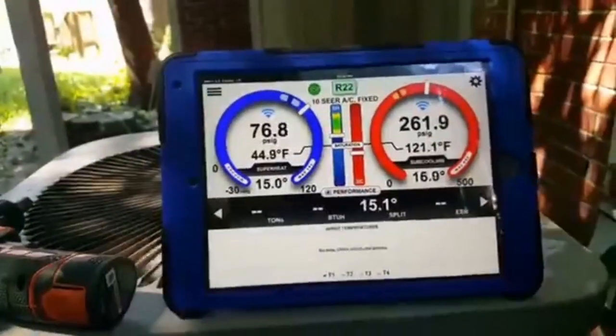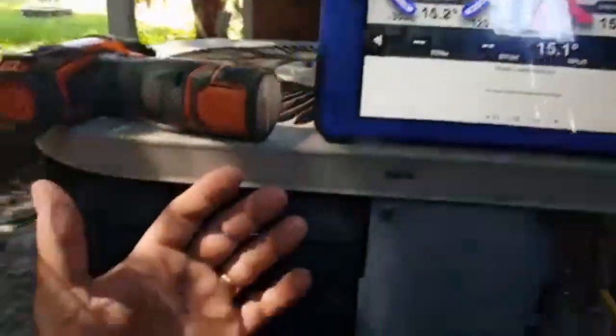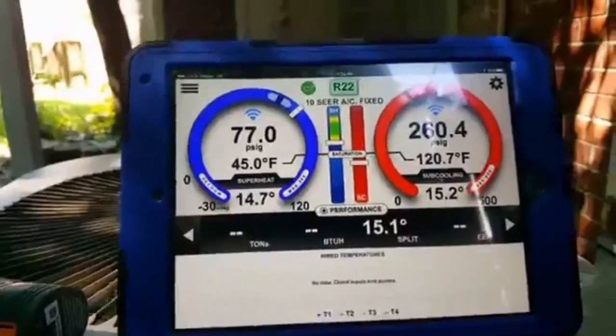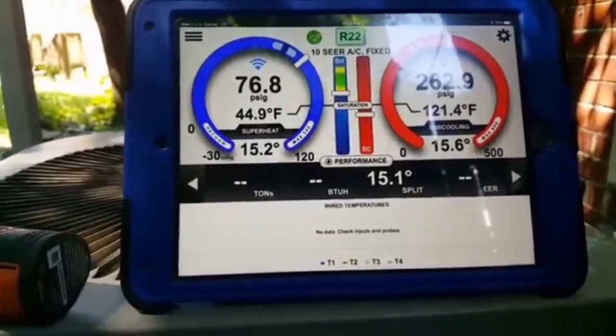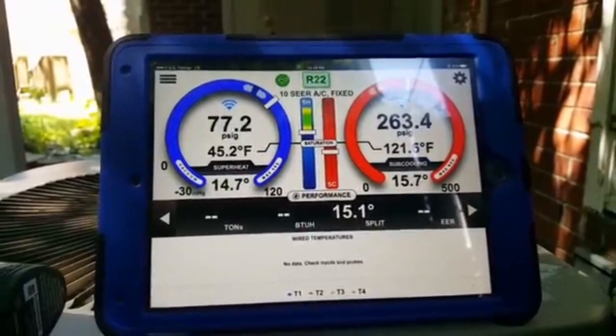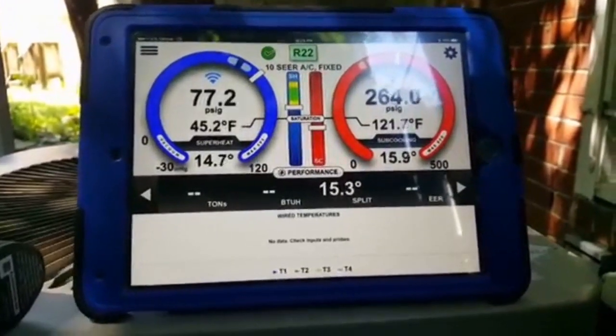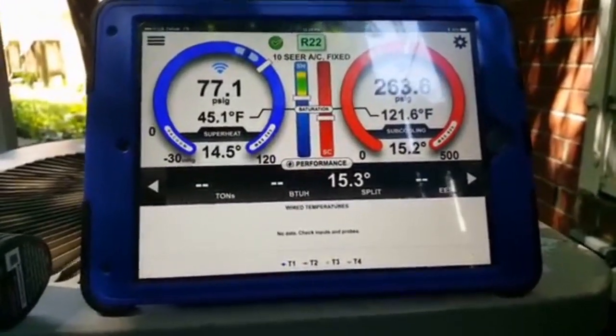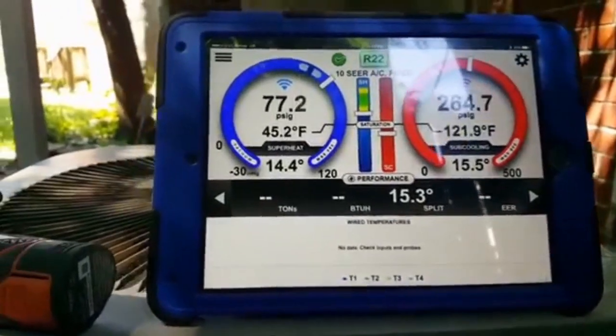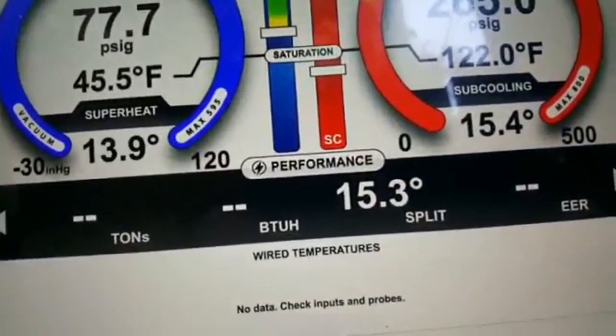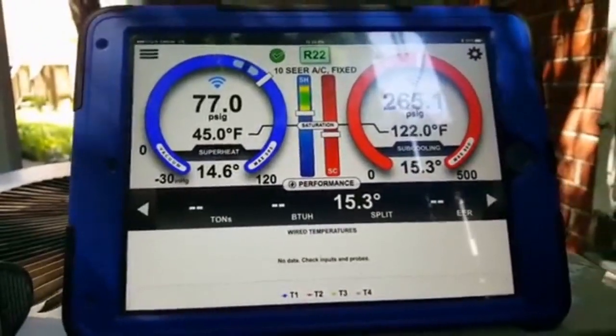Well, she's running a little bit above target, and we're not getting good airflow out of the top of the condenser here, we're getting a little bit out the side of it. So we might have a non-OEM fan motor. The blade probably looks fine, maybe the motor itself is not, that's why we're getting these skewed numbers. It's still cooling inside, but my numbers are definitely high.